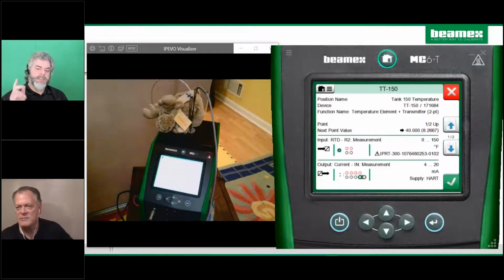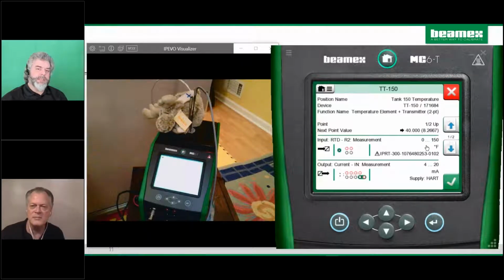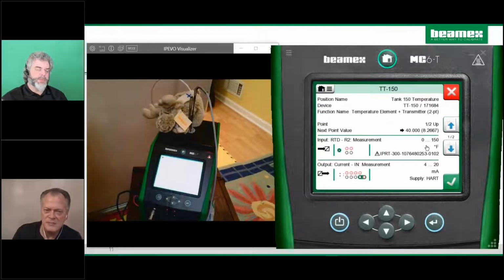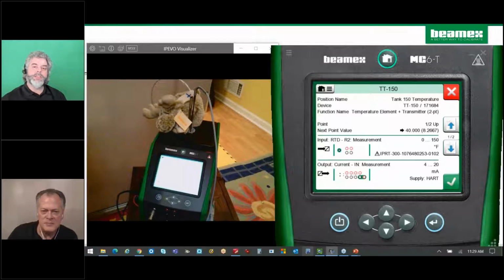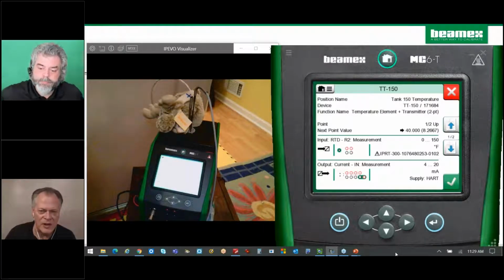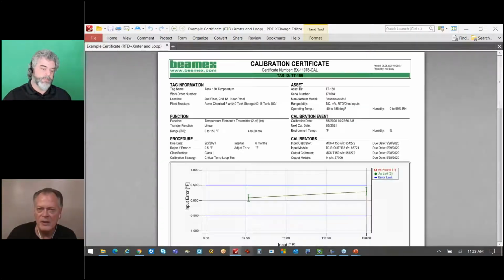This might be something that isn't obvious, that you can have an offset in the DCS and it's not related to the transmitter. The only way to know is to grab all this data. You grabbed information on the transmitter, you grabbed information on the DCS, and you can see where they're different. You could go into the DCS and do an offset so that it showed exactly 150 or exactly 40. With this kind of equipment and test methods, you can really display a very close to true temperature in the control room. You can really do some accurate work.